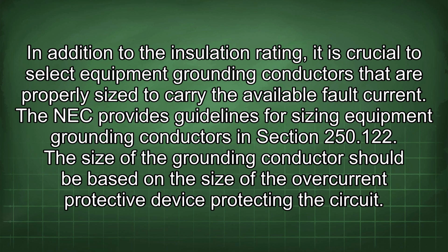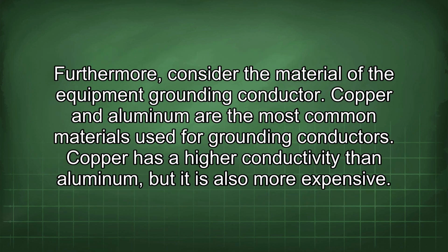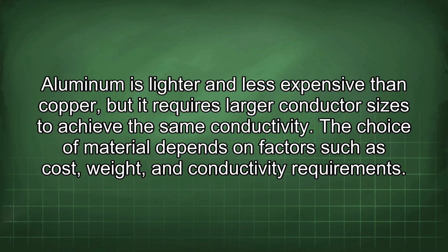In addition to the insulation rating, it is crucial to select equipment grounding conductors that are properly sized to carry the available fault current. The NEC provides guidelines for sizing equipment grounding conductors in Section 250.122. The size of the grounding conductor should be based on the size of the overcurrent protective device protecting the circuit. Furthermore, consider the material of the equipment grounding conductor. Copper and aluminum are the most common materials used for grounding conductors. Copper has a higher conductivity than aluminum, but it is also more expensive. Aluminum is lighter and less expensive than copper, but it requires larger conductor sizes to achieve the same conductivity. The choice of material depends on factors such as cost, weight, and conductivity requirements.